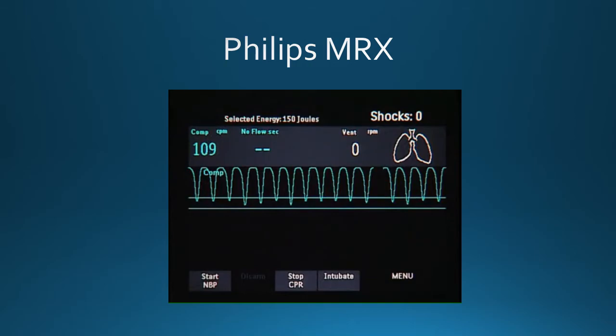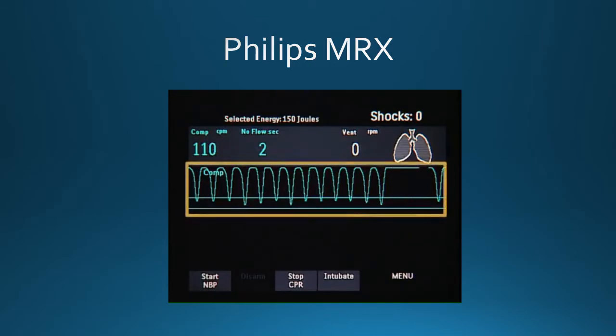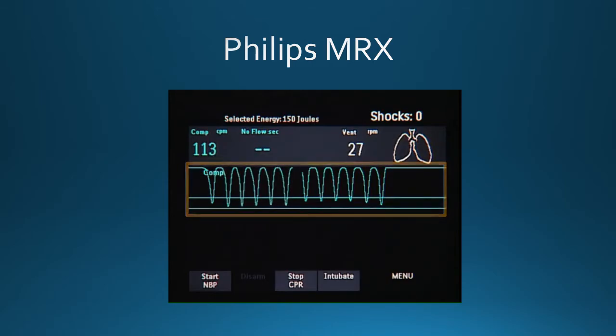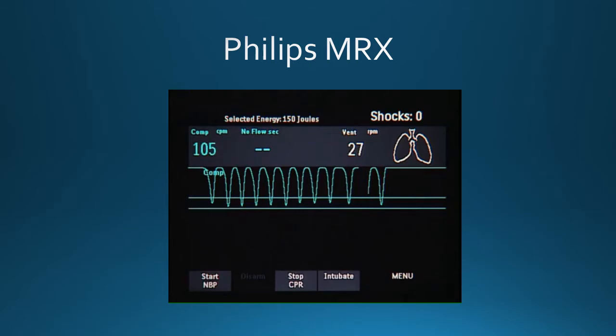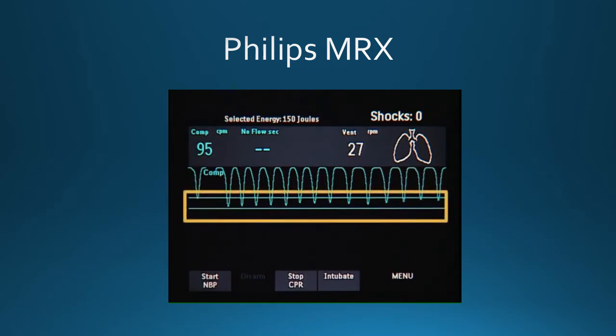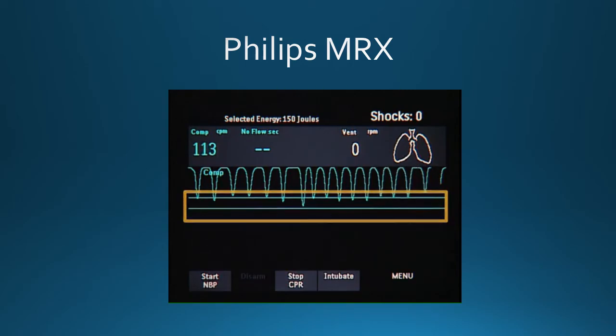In manual mode, the compression waveform appears here and is labeled comp. As the chest is compressed, the wave's downward stroke occurs. As pressure is released, the wave rebounds up to a baseline. These lines define a target zone to help you achieve good compression depth, which is accomplished when the compression peak of the waveform appears between the lines.